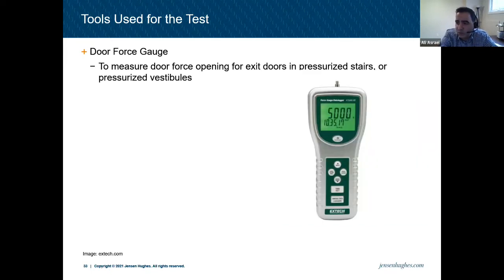Another device is a door force gauge. This is obviously to measure the door opening force. We talked about it in exit doors or any pressurized area, pressurized vestibule. We need to make sure that the doors can be opened by the occupants. Excuse me. So yeah, we use that device. I talked about that 130 Newton in SB4 and 90 Newton in OBC. So there are these different things where it comes down to your judgment. So we're going to talk about it at the end, the engineer's judgment, which number they're going to accept.